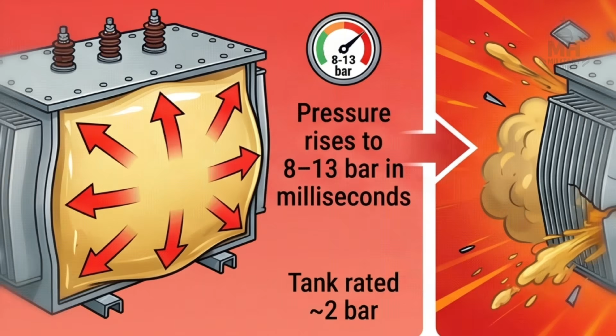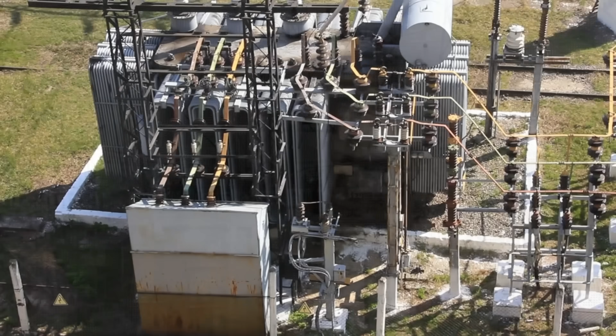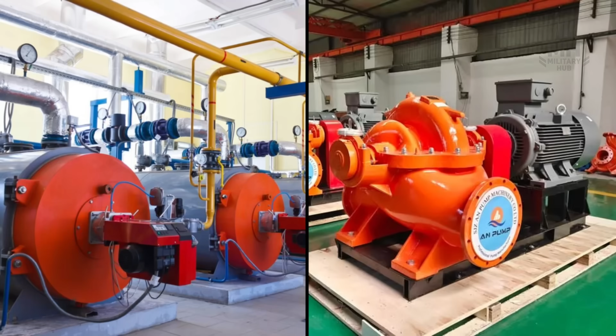What follows is a boiling liquid expanding vapor explosion, a BLEVE, that can produce thermal radiation intense enough to cause fatal burns at a distance of 90 meters and demolish structures even further out. 30 tons of oil makes for a very large BLEVE. A transformer of this class, 10,000 kilowatts or 10 megawatts, is not a small neighborhood unit. It sits at the interface between generation and distribution, stepping power down from high-voltage transmission lines to the levels required by the heating plant's boilers and pumps. Losing one does not just mean a blackout. In a combined heat and power system like Bucharest's, it can mean a loss of thermal output to entire districts, particularly devastating during winter, though even in spring the disruption to hot water supply affects hundreds of thousands of residents.